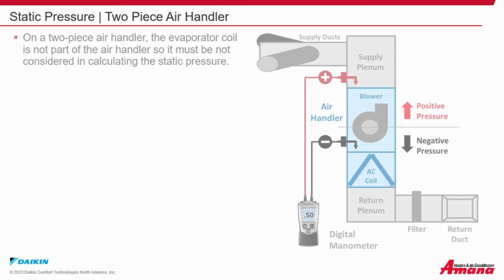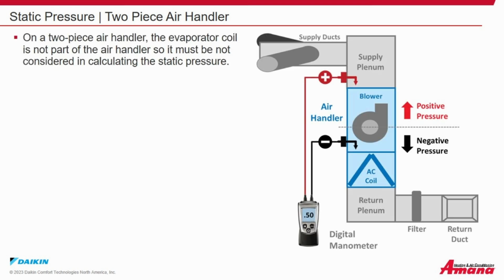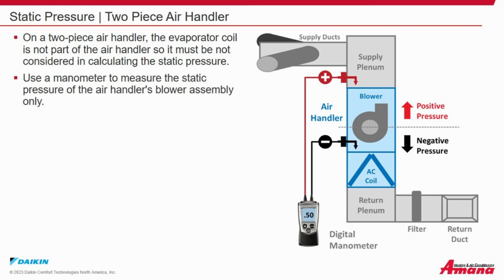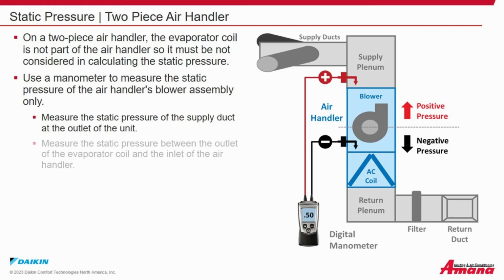Static pressure, two-piece air handler. On a two-piece air handler, the evaporator coil is not part of the air handler, so it must not be considered in calculating the static pressure. Use a manometer to measure the static pressure of the air handler's blower assembly only. Measure the static pressure of the supply duct at the outlet of the unit. Measure the static pressure between the outlet of the evaporator coil and the inlet of the air handler.